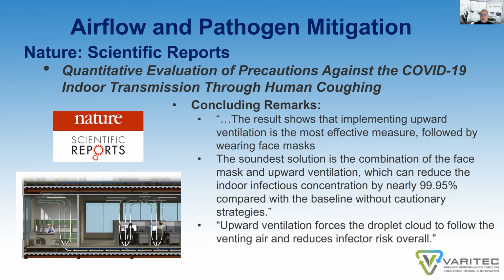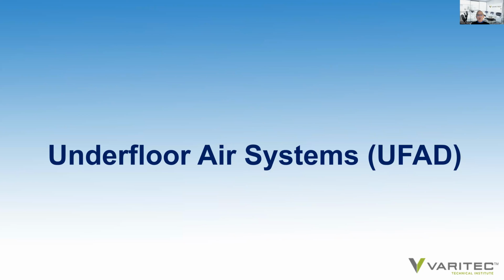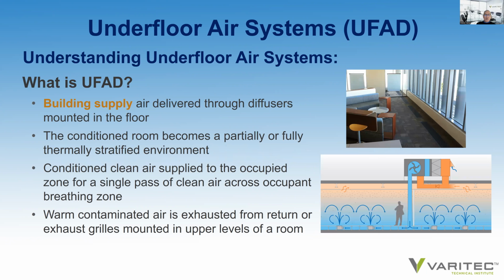The soundest solution to reduce the risk of infection in a space, the article proposes, is the combination of the face mask and upward ventilation, which can reduce the indoor infectious concentration by nearly 99.95%. It goes on to say that upward ventilation forces the droplet cloud to follow the venting air, which is from the occupied zone to the upper levels of the room, thereby reducing the risk of infection. So that's pretty compelling. So what type of system will provide for an upward airflow or vertical airflow solution to a building? Well, underfloor air systems are that system to be considered.